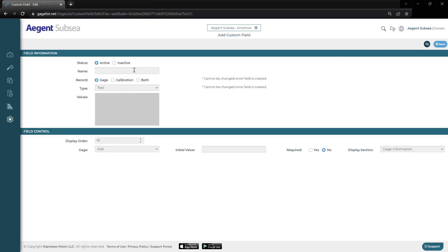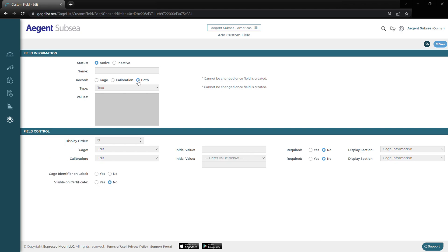Here we can choose the name of our custom field. Below that, we can choose the record type: the gauge record, calibration record, or both. Keep in mind, this can't be changed once it's created. So if you're ever unsure, I always recommend going with both, because you can make it inactive on the record that you don't want it on, so that way you keep things open-ended.